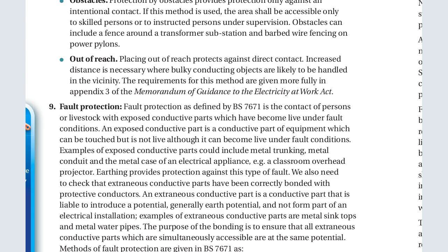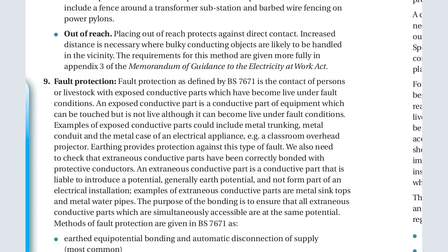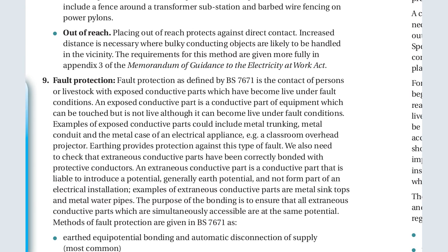So we'll also need to check that extraneous conductive parts have been correctly bonded with protective conductors. An extraneous conductive part is a conductive part that is liable to introduce a potential, generally earth potential, and does not form part of an electrical installation. For example, extraneous conductive parts are the metal sinks, tops, and this one is also on bonding. Normally when an installation is done, we have something called bonding, where equipotential bonding is the connection of all the metallic parts in the house, all the metallic sections in the house, connecting them to the main earthing system.